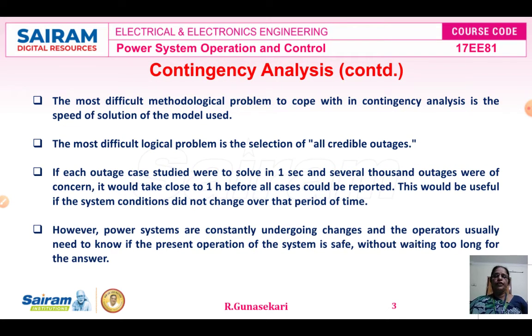The most difficult methodological problem in contingency analysis is the speed of the solution of the model used, that is, the algorithm used. The most difficult logical problem is the selection of all credible outages. If each outage case study were to be solved in 1 second and several thousand outages were of concern, it would take close to 1 hour before all cases could be reported.